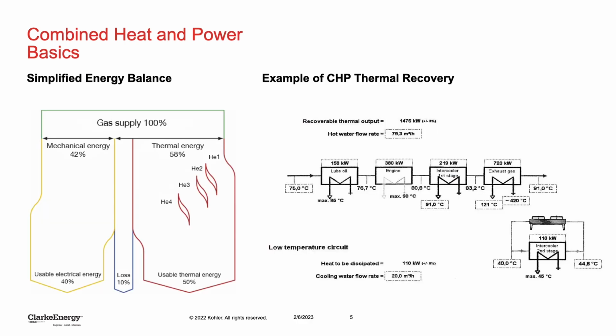CHP module basics on a simple level consist of an energy balance. When you consider 100% of the energy in the fuel gas, it's typically converted at electrical energy efficiency of around 40 to 46%. Thermal energy recovered from the engine cooling circuits and the engine exhaust is typically somewhere between 40 and 50%, giving a total energy efficiency of 90% with roughly 10% losses.